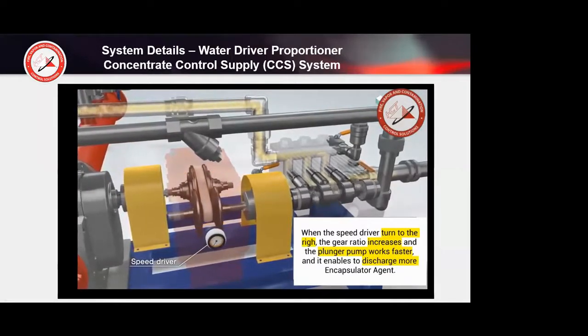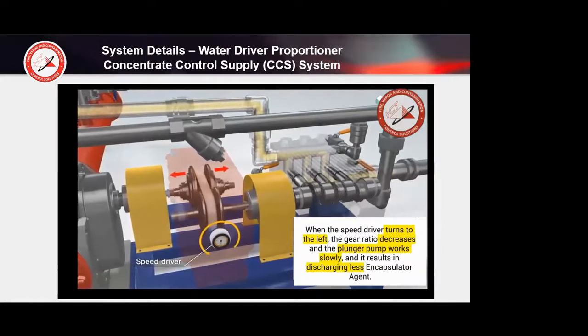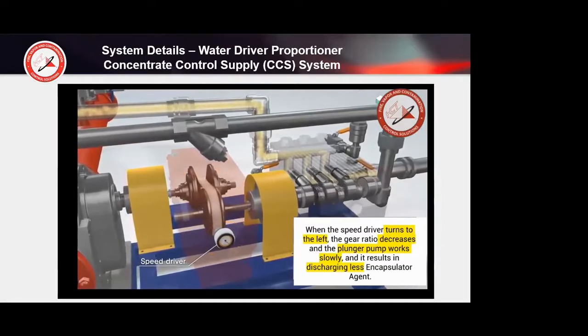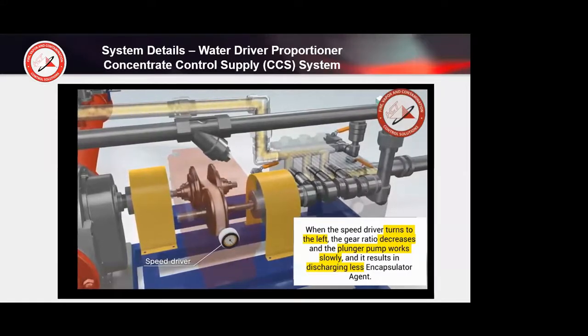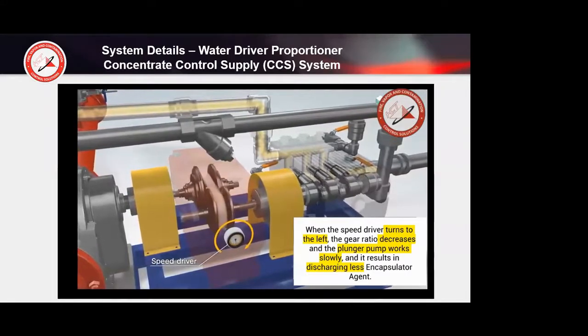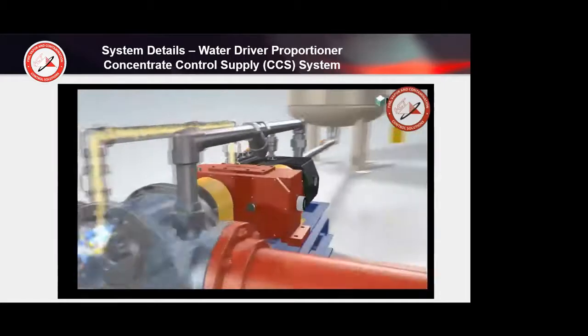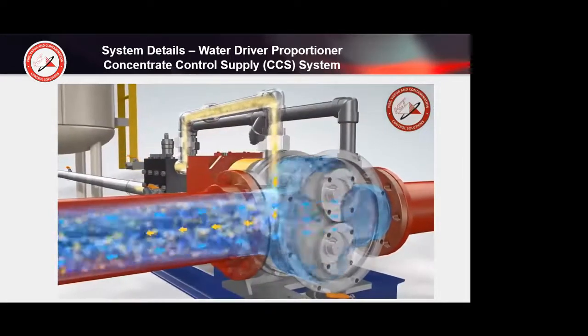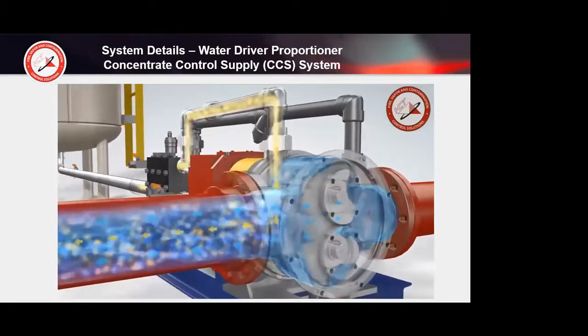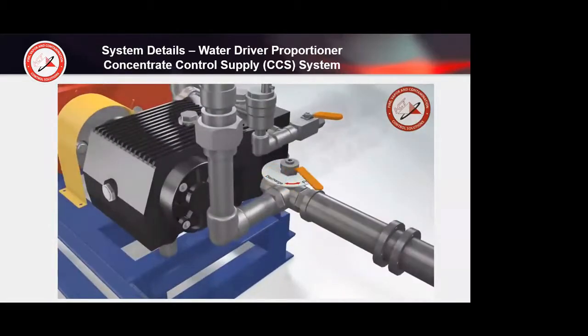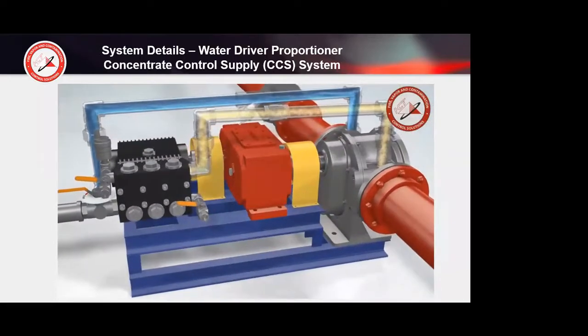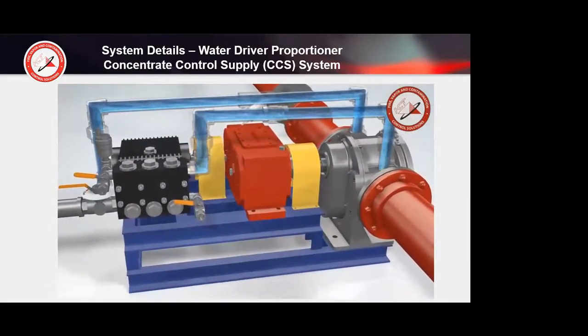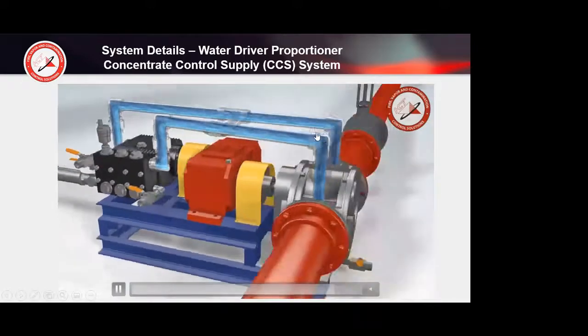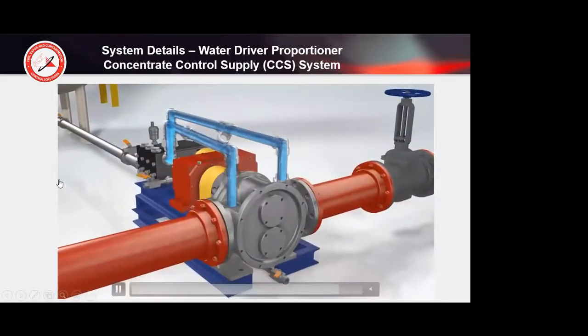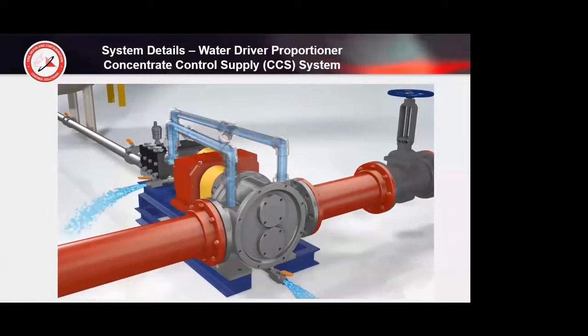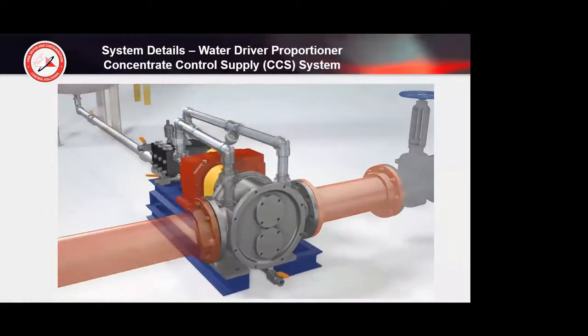Most systems are standard, either a 1% or a 3% system. Some of them you can get a speed adjuster here to adjust from a 1 to a 3. Those may be mounted on a fire truck, for example. Let's say every system we've put in so far is either a 1% or a 3% fixed system based on the hazard. So here it's just showing a flush. After you're done, you just flush out. And then when it comes time to fill the tank, usually it's just pop the lid off the tank, pump more agent in, and you're ready to go.